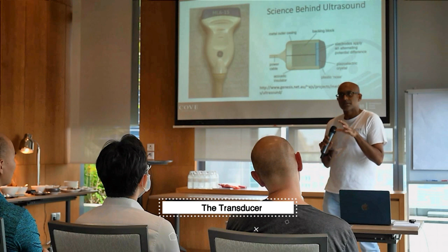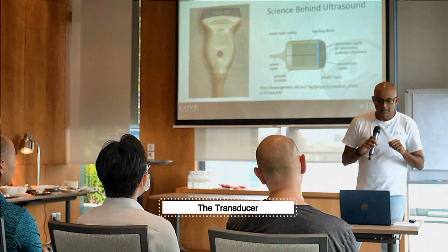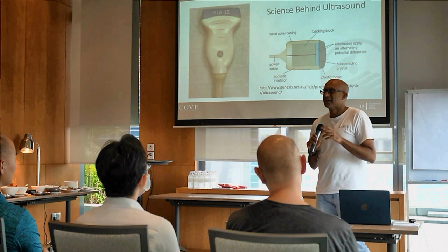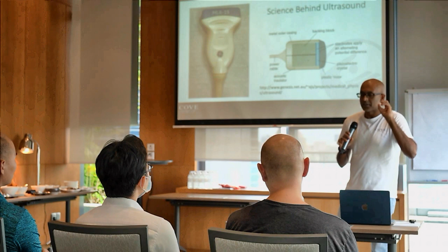But the key component is the transducer. Having a quality transducer is really, really important, and understanding how to look after it is also very important. God knows I've cringed a few times when my trainees used to drop the transducer and go, oops. That's like $10,000 you just busted there. The key component is this area here, the piezoelectric crystals. When you get an electrical signal over these piezoelectric crystals, it emits a sound wave into the tissue. When the sound wave hits a structure, part of it gets reflected back to the piezoelectric crystals, which then create another electrical signal, send it up to the machine, and then you get the images.